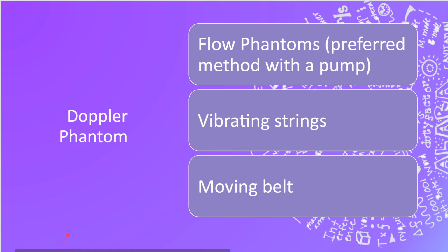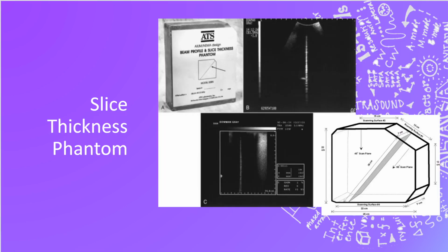The last type of phantom that we talked about then is the slice thickness phantom, or the elevational resolution. So with the slice thickness phantom, or the beam profile phantom, it's going to allow us to see the shape of the beam. What these look like, they again are made of that soft tissue jelly material. And through the middle of it, we'll use this one down here, through the middle of it is this flat bar. And you scan from the surface that's 45 degrees to the bar.